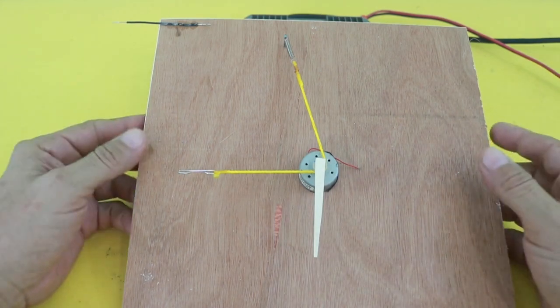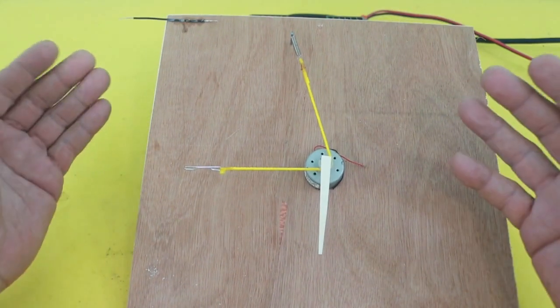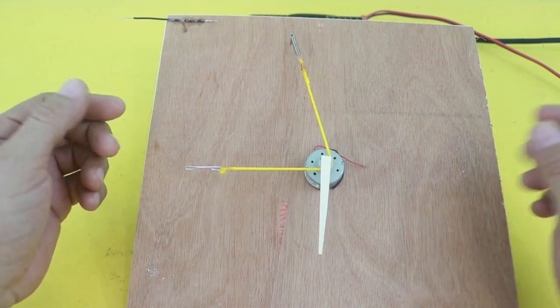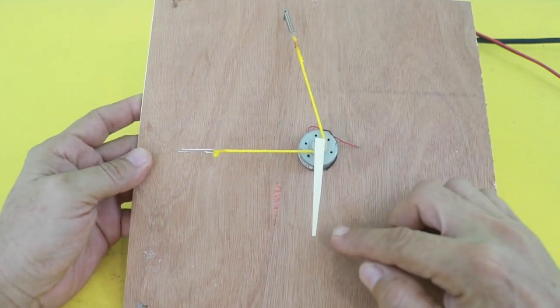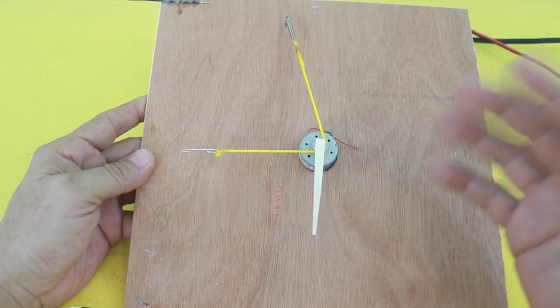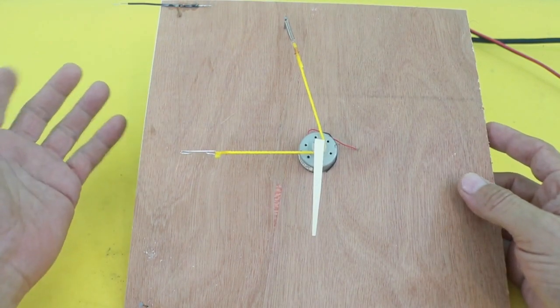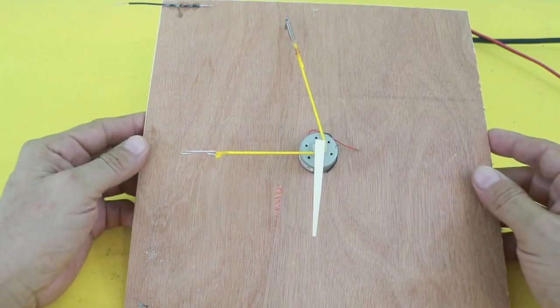Also, it depends on the ambient temperature because that will change the calibration of the instrument. If it is hot or cold, the wire is at a different temperature and the calibration is lost.